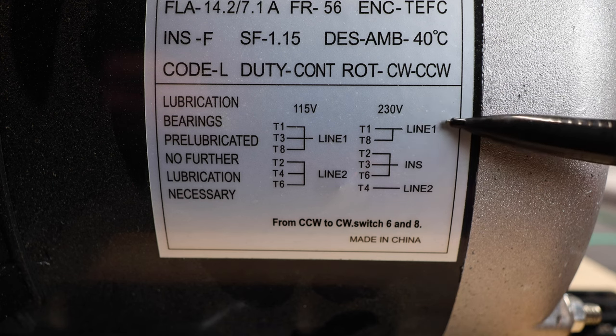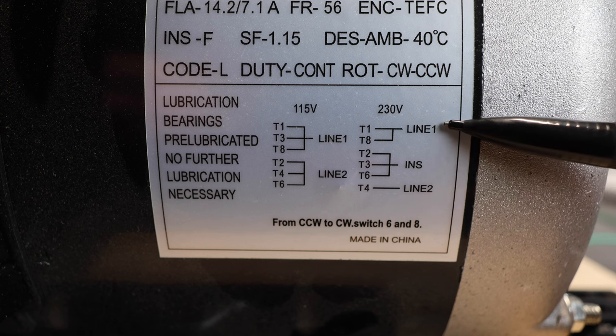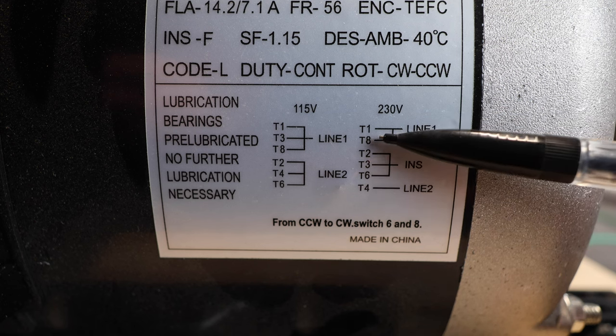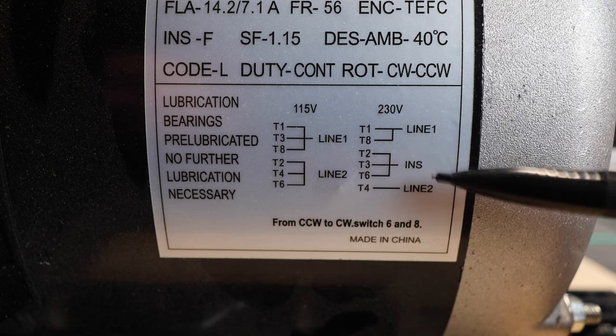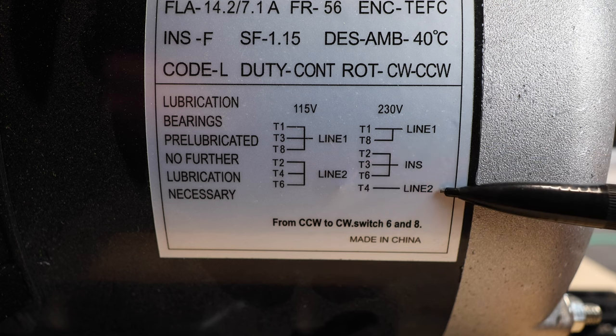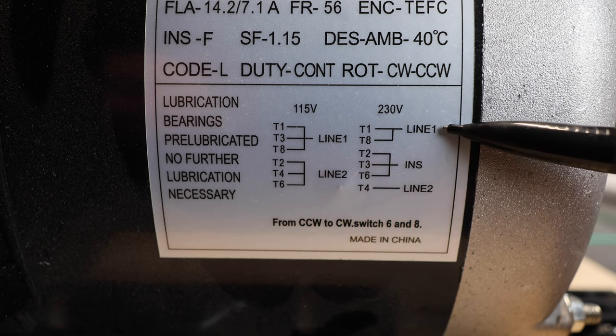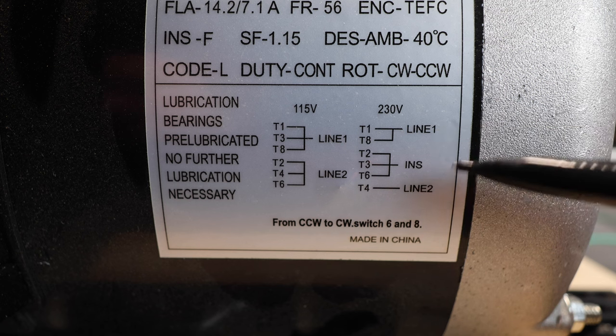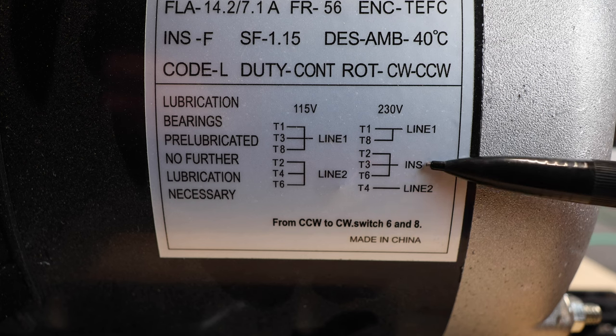Now if we start looking at the actual diagram over here for our high voltage side, we can see that line one will need to be connected to T1 and T8. The T2, T3, and T6 will just be insulated and connected together. And then finally, L2 will be connected over here to our T4. Now just to point this out, because I got another question on this, was these line one and line two, this is your incoming power. So these are your power wires coming into the motor. And then again, this just means insulated, so you're just connecting all those wires together.